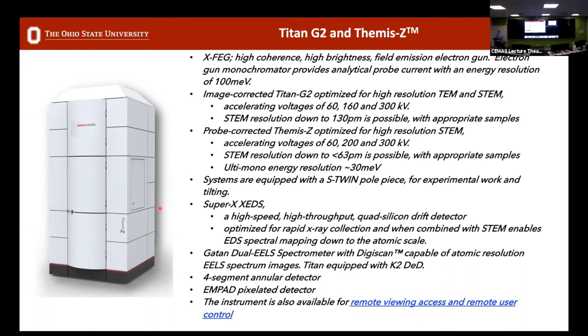Both systems have an XFEG, which provides a high-coherence, high-brightness field emission electron gun. The monochromator allows us to vary the current in real time to increase signal-to-noise or decrease dose rate — a very powerful analytical tool most TEMs don't have. We have a monochromator that provides the ability to increase energy resolution to around 100 millielectron volts — 0.1 eV. For those familiar with synchrotron data, you have around 0.1 eV energy spread, which allows near-edge analysis for compositions and bonding. The same applies here — we can reduce the energy spread and really open up spectral characterization.